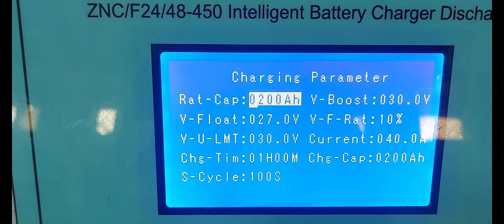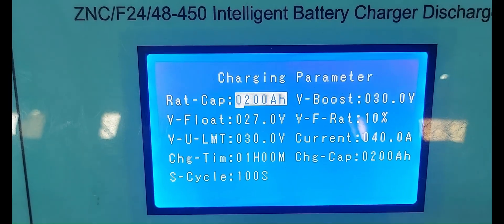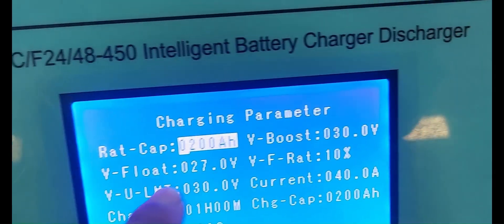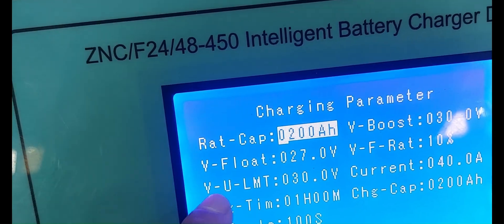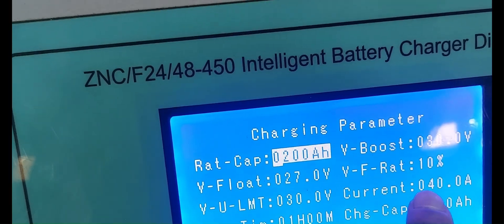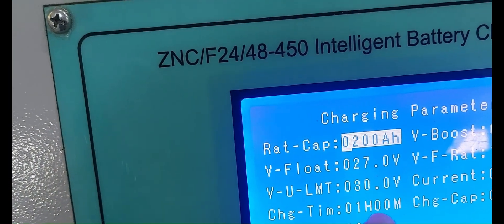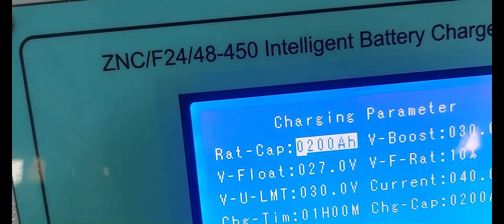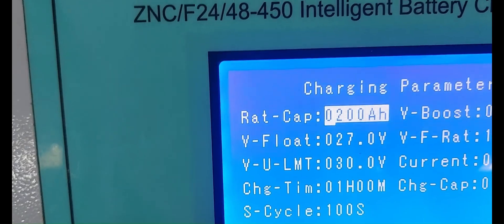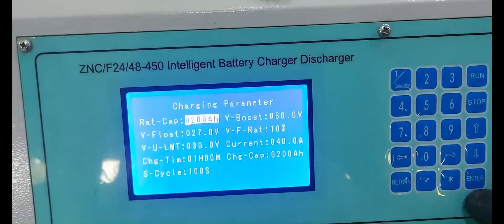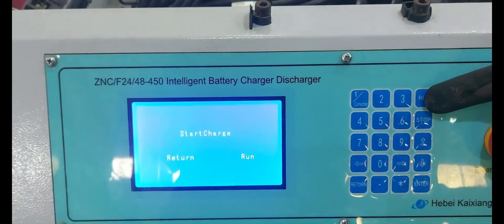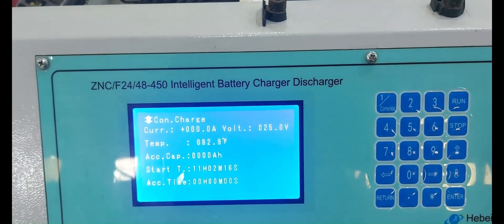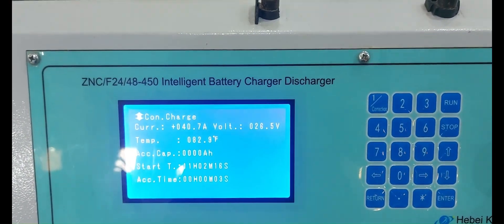Next, we are configuring the charging parameters. First, we are setting the rated capacity of the battery — that is 200 Ah, already set. Next, we are checking the boost voltage — already configured at 30 volts. Float voltage — already setting at 27 volts. 30 VDC current, charging current 40 amps, charging time 1 hour. Next, we press the Enter button and then the Run key — now charging is enabled and on hold.